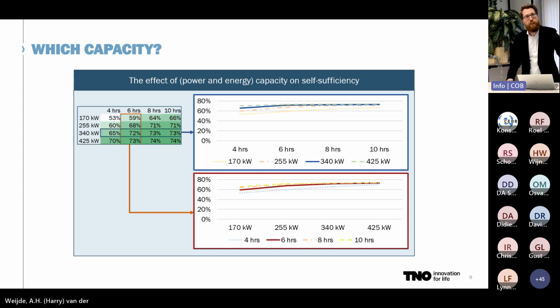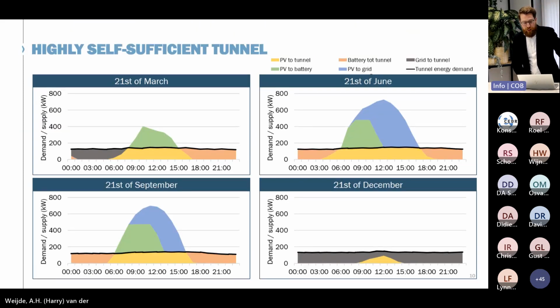So, 6 hours of storage at 340 kilowatts. This tunnel has a demand, shown here over a couple of days, that is slightly below 200 kilowatts generally, but it can peak much higher if there's an emergency. Here you see what happens if you install this battery in a tunnel on four days during the year. The easiest case is in December: on a cloudy day in December, almost all the electricity the tunnel needs still comes from the grid connection, shown in gray.